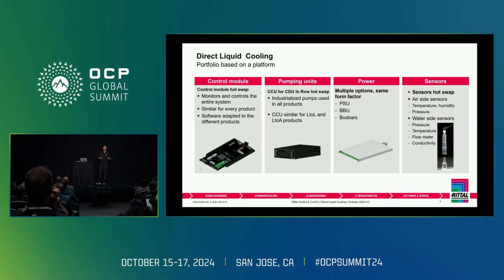We've been able to do that because of our platform-based architecture approach. Most of the components are highly standardized across our whole range, from the control module to the pumping modules to power and all the sensors within it. For example, on the pumping modules, we have the same form factor for what we have on the in-rack CDUs, up to 150 kilowatts with heat exchanger built in, up to the 1 megawatt unit, which is a standalone pumping unit with a capacity of up to 250 kilowatts of actual pumping capacity.